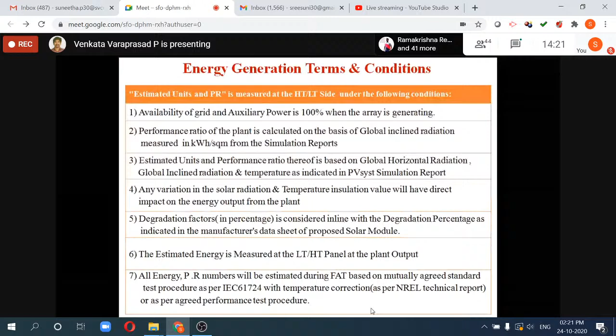Here you can see the solar power plant: how many modules are there, and how many modules are erected in each block, each module having a capacity of 320 watts. Block 1 has a module capacity of 320 watts, and 140 modules are erected in this block. Calculating this, 140 modules at 320 watts each gives us 44.8 kilowatts DC power, and after conversion, 50 kilowatts AC.